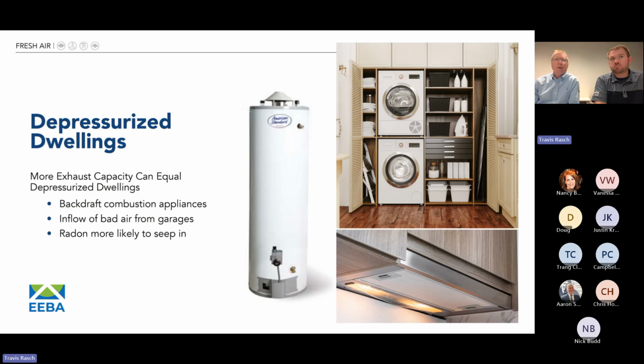Another aspect we want to think about is depressurizing dwellings. So this can be a concern if you build a very tight dwelling, which we want to do, of course. And then if you run a very high CFM range hood, or you're running your range hood and your dryer that's pulling out 250 CFM, we could potentially backdraft things like gas hot water heaters. We don't want carbon monoxide coming back into the room, of course. So something to think about. It could also pull in radon from under your subslab, could pull in pollutants like gas or whatever you're storing in your garage, leftover exhaust fumes from your car. So, think about really tight homes. You don't want a lot of exhaust devices running at the same time.